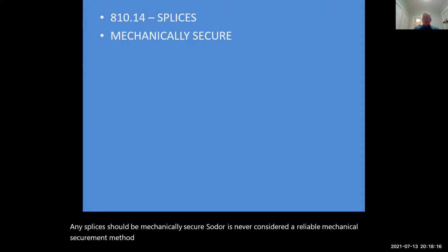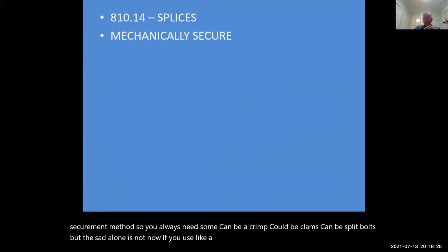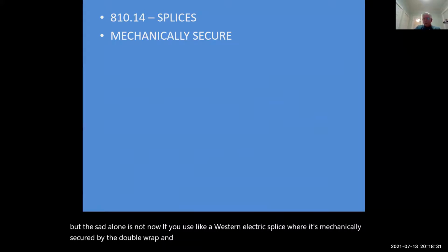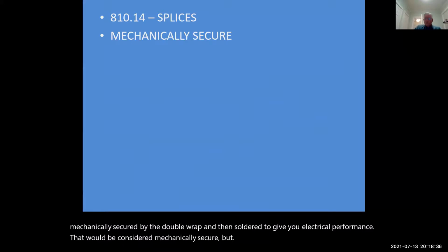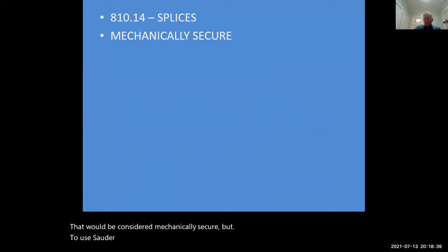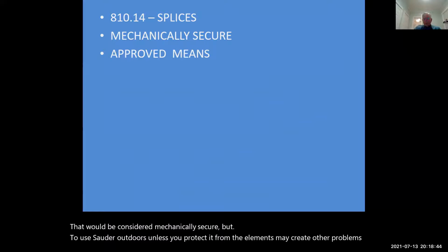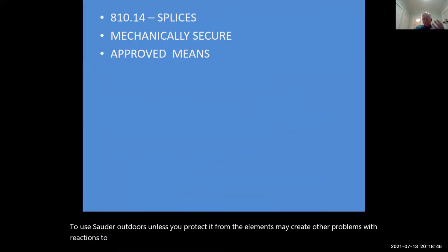So you always need some method, it can be a crimp, clamps, or split bolts, but solder alone is not enough. Now, if you use something like a Western Electric splice, where it's mechanically secured by the double wrap and then soldered to give you electrical performance, that would be considered mechanically secure. But using solder outdoors, unless you protect it from the elements, may create other problems with reactions to the rain, especially if you're in an area that has anything in the air, whether it's an acid rain type situation.